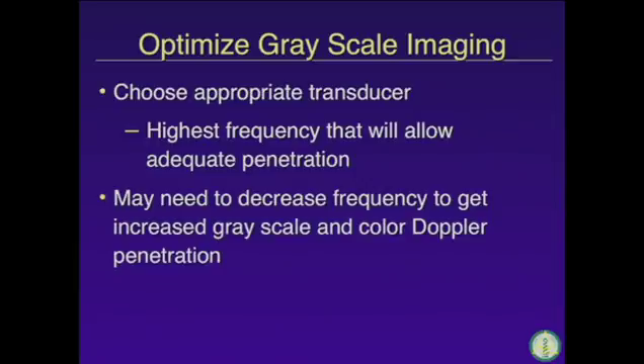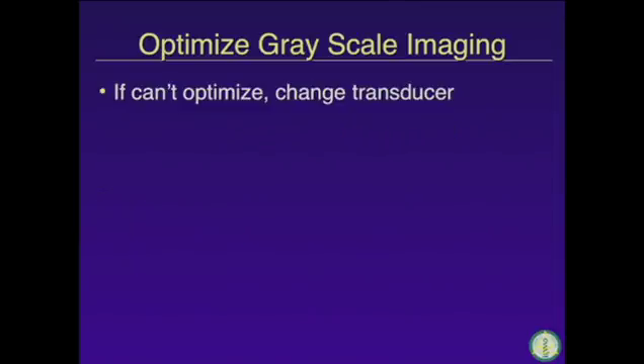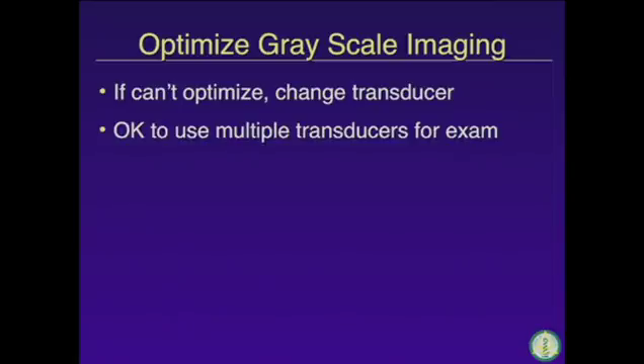With that same first transducer though, you may need to decrease the frequency because sometimes you can shift frequencies in a given transducer. So you may need to decrease the frequency to get increased grayscale and color Doppler penetration. So once you get past the grayscale, you may either have to decrease the frequency to optimize your Doppler imaging or to go to a different transducer altogether. So if you can't optimize, change the transducer. And it's okay to use multiple transducers for an exam.